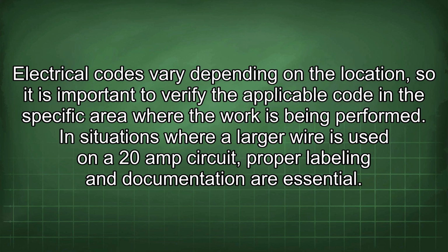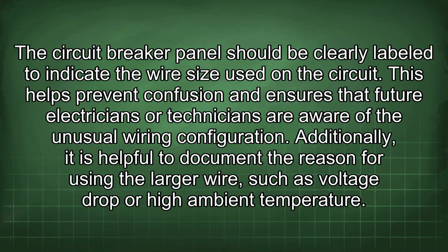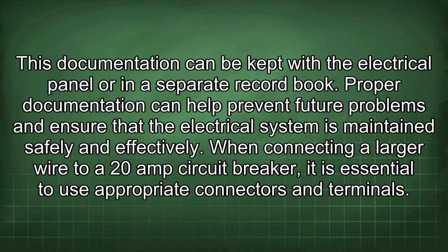In situations where a larger wire is used on a 20-amp circuit, proper labeling and documentation are essential. The circuit breaker panel should be clearly labeled to indicate the wire size used on the circuit. This helps prevent confusion and ensures that future electricians or technicians are aware of the unusual wiring configuration. Additionally, it is helpful to document the reason for using the larger wire, such as voltage drop or high ambient temperature. This documentation can be kept with the electrical panel or in a separate record book. Proper documentation can help prevent future problems and ensure that the electrical system is maintained safely and effectively.